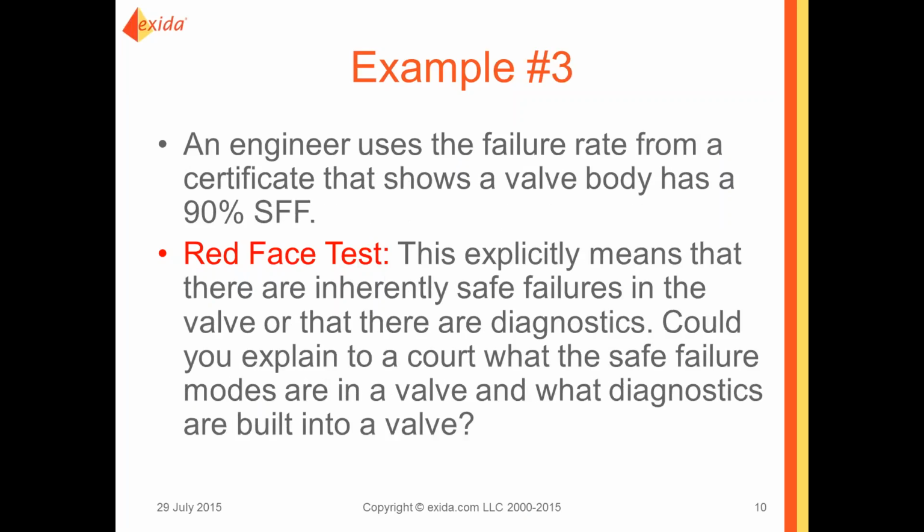Example 3. An engineer uses a failure rate from a certificate that shows a valve body has a safe failure fraction of 90%. So the red face test is, this explicitly means there are inherent safe failures in the valve body, or that there is a high degree of diagnostic coverage. Could you explain to a court what the safe failure modes of your valve were, or what built-in diagnostics there were?